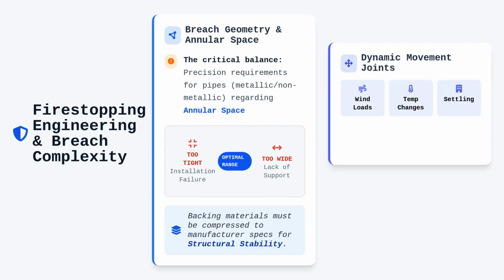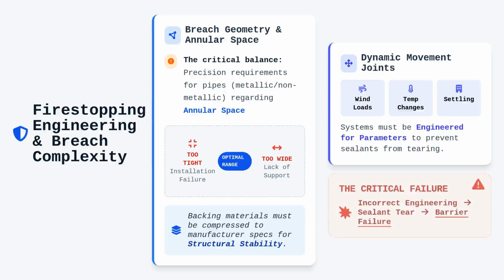We must also consider the dynamic nature of movement joints. These joints are not static. They shift due to wind loads, temperature changes, or building settling. If the fire stopping system is not engineered for these specific movement parameters, the sealant will tear, eventually creating a failure point that defeats the entire barrier design.